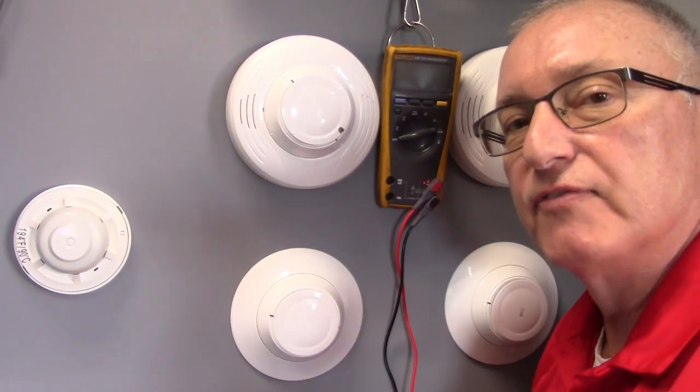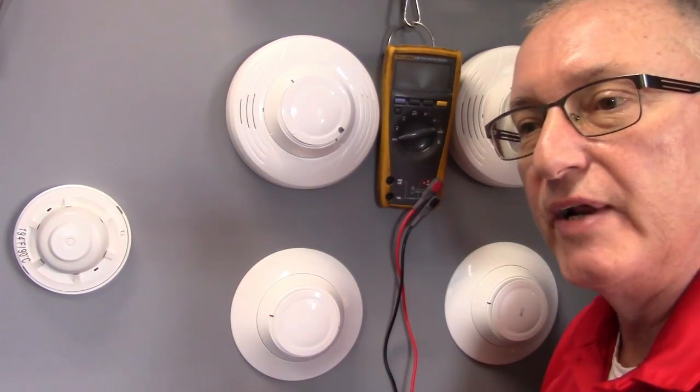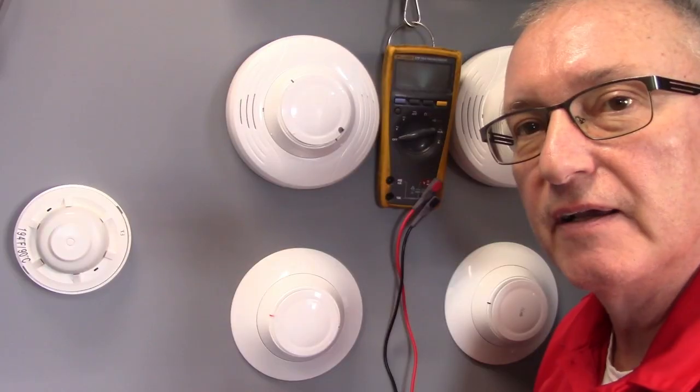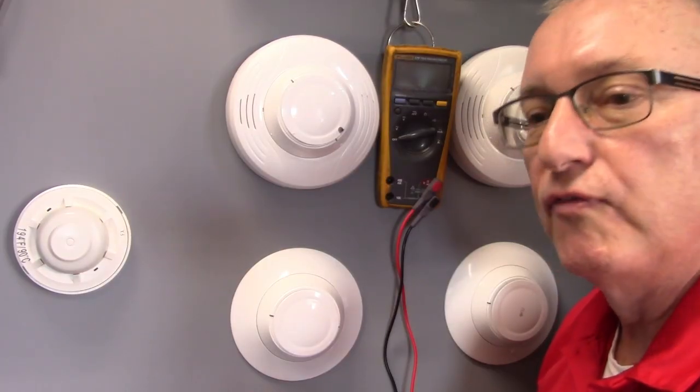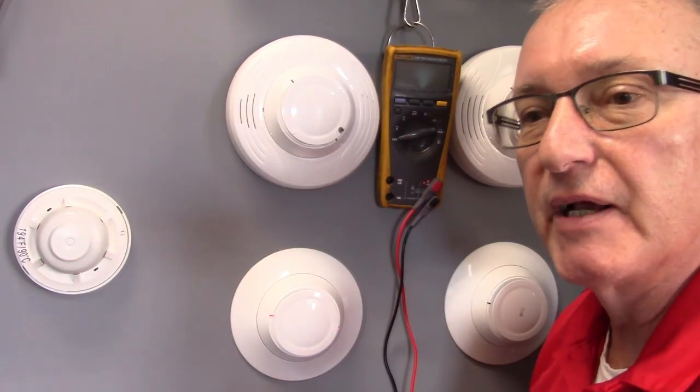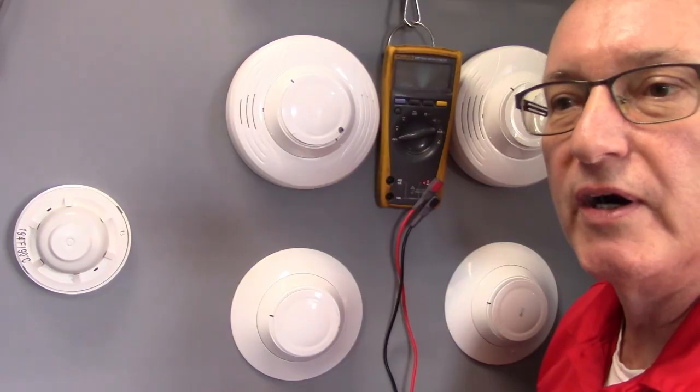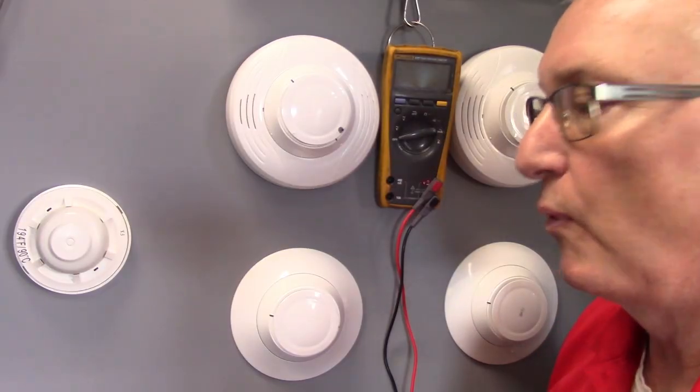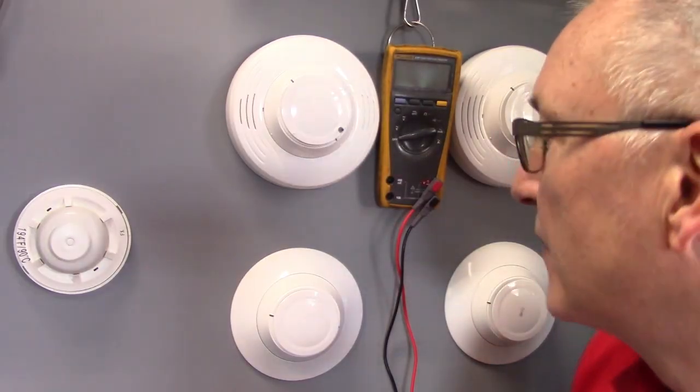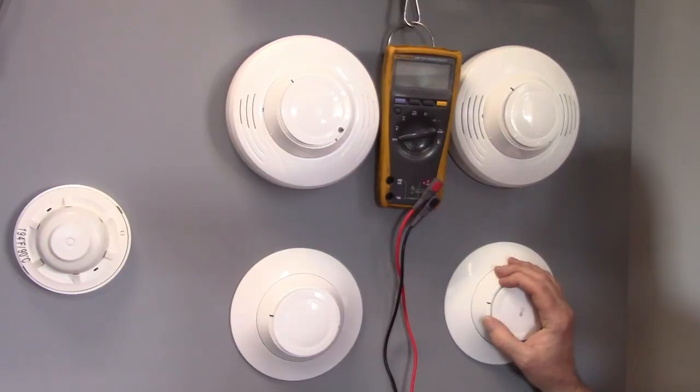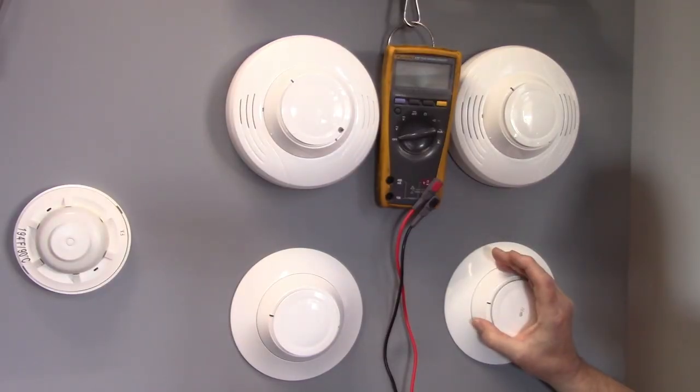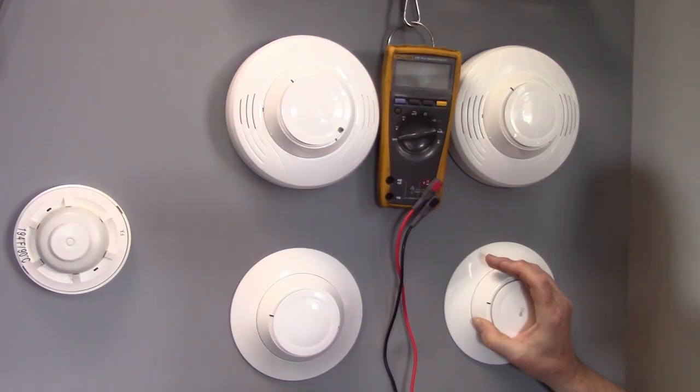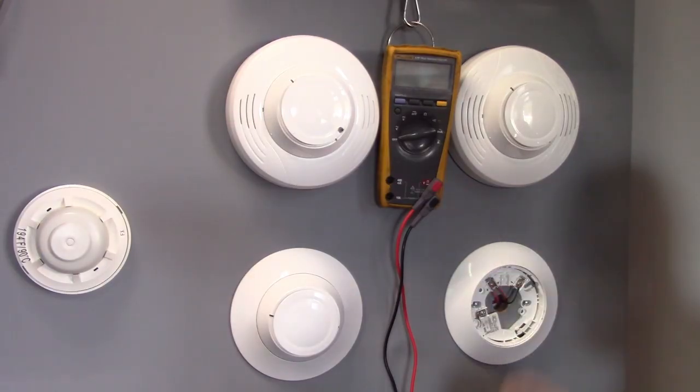Once you've identified the circuit leaving the fire alarm panel that has the ground fault, now you're going to have to walk away from the fire panel, go out into the building, look for that circuit, and try to pick a point somewhere in the middle, a halfway point if you will. It's probably just going to be a guess. You pick yourself a halfway point. You're going to need to open the circuit and take some measurements.